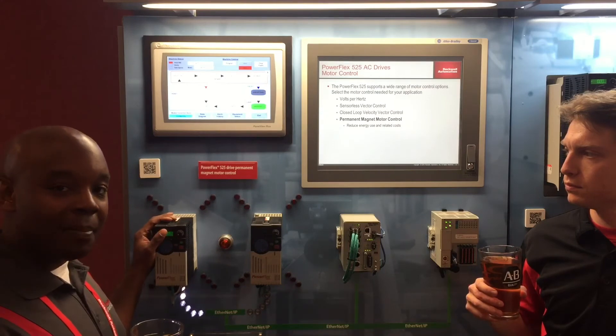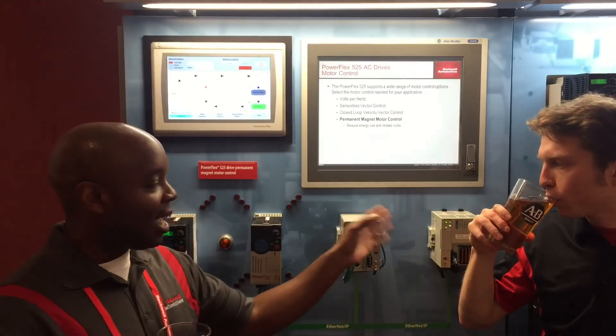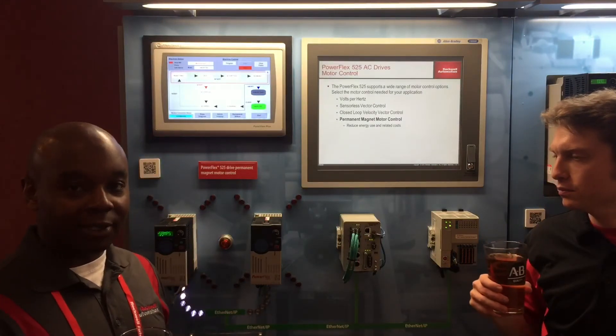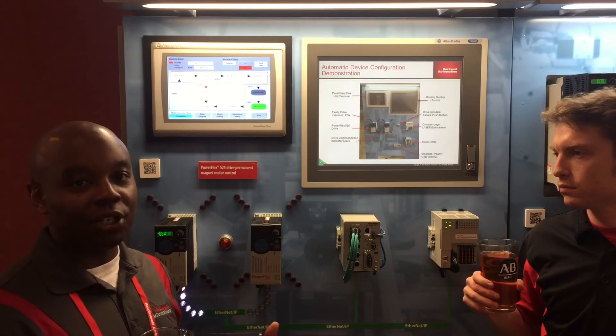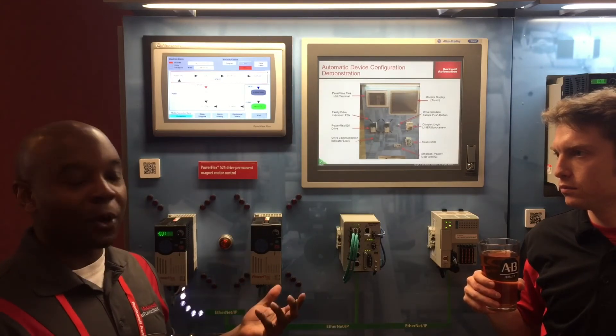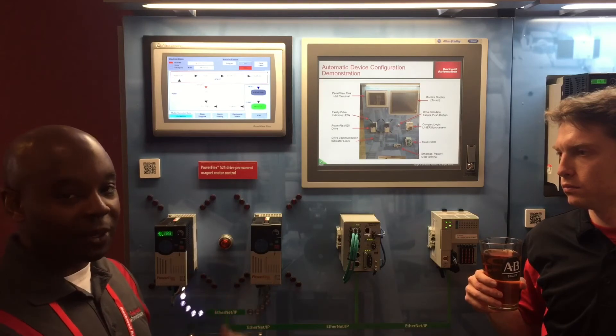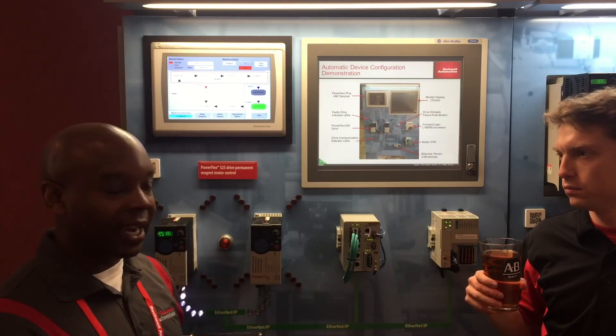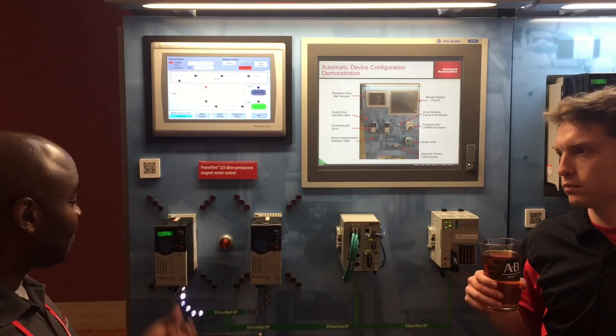All of the parameters are configured to be identical to the product that you're replacing on the line. In order for this to work, you have a PowerFlex drive with embedded Ethernet, along with a managed Stratix switch, and of course a Rockwell PLC. Using all the power of Premier Integration and Studio 5000, you have Firmware Supervisor and automatic device configure — now your downtime is reduced from a few hours of configuring a new drive to only a few minutes.